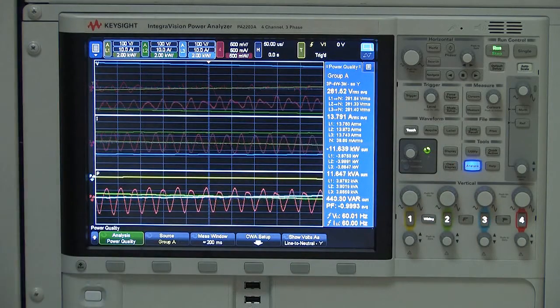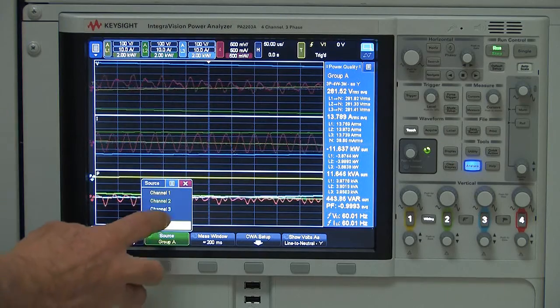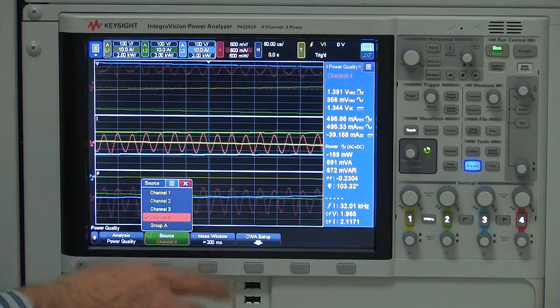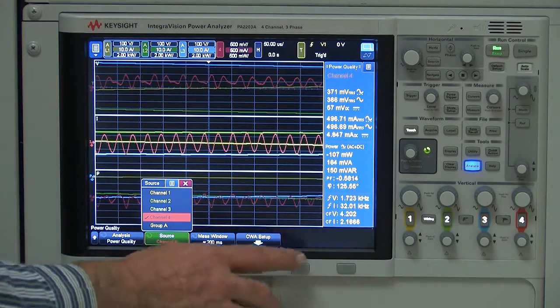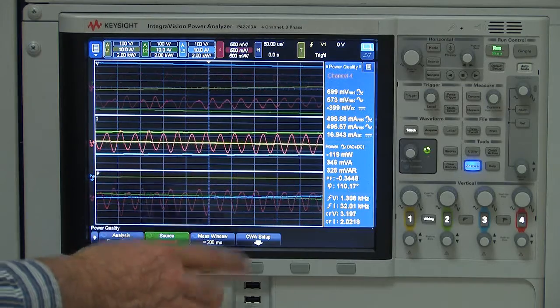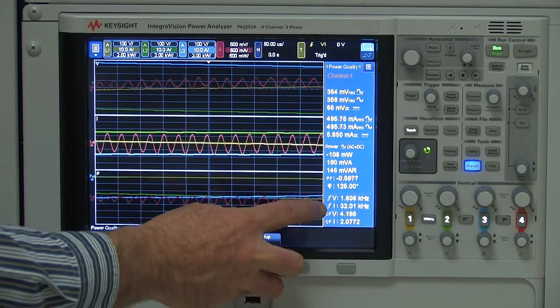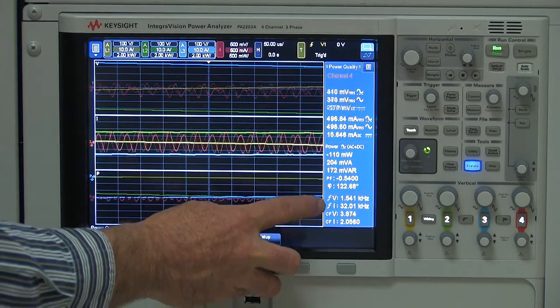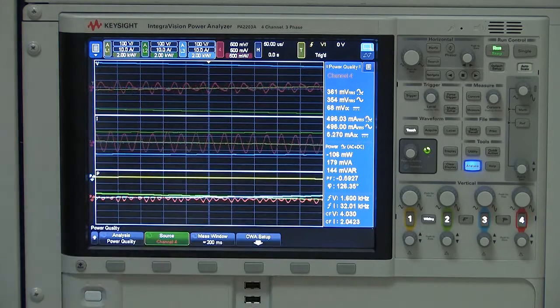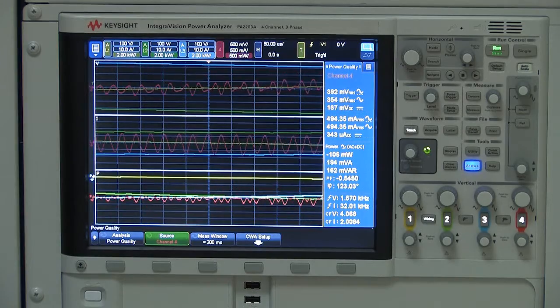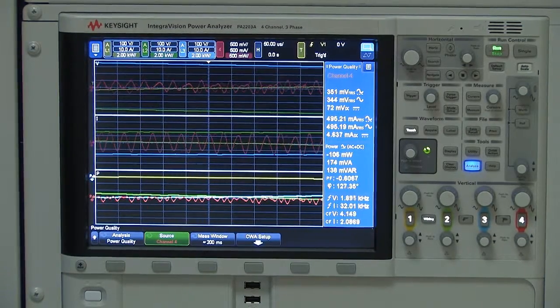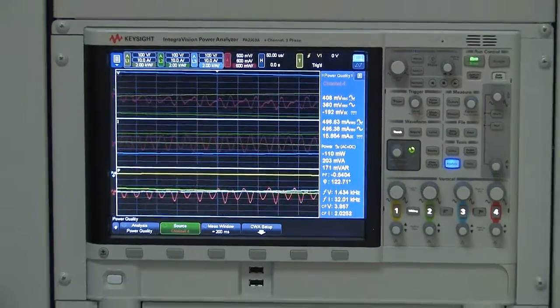Come over to my power analysis, switch over to channel 4. And I can see that the frequency of the current waveform has an AC signal on it at 32 kilohertz, which I suspect is actually the switching frequency of the inverter itself. So by AC coupling on the waveform, we're able to remove the DC offset, zoom in on the signal, and actually see the switching waveform.